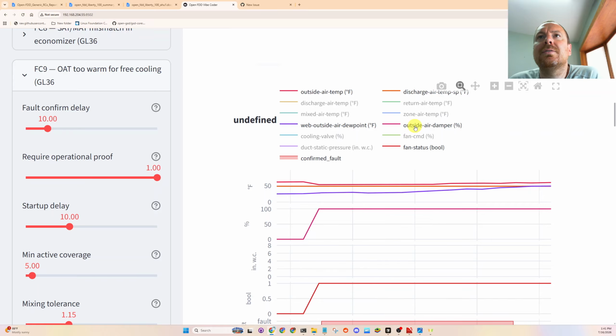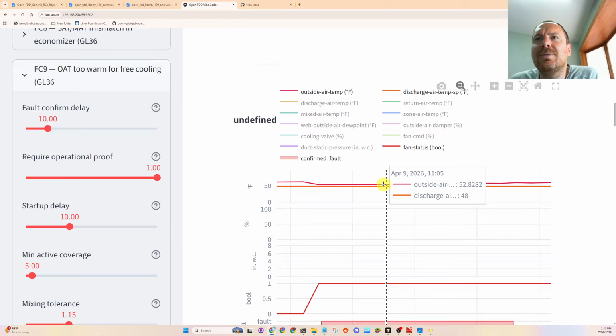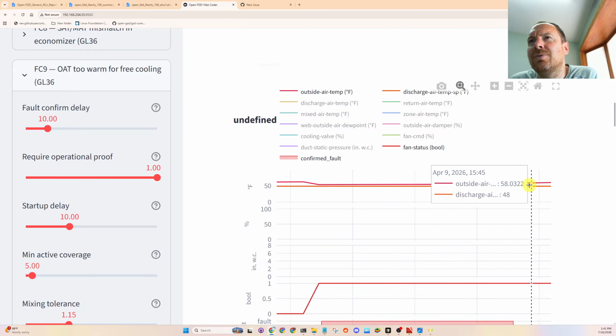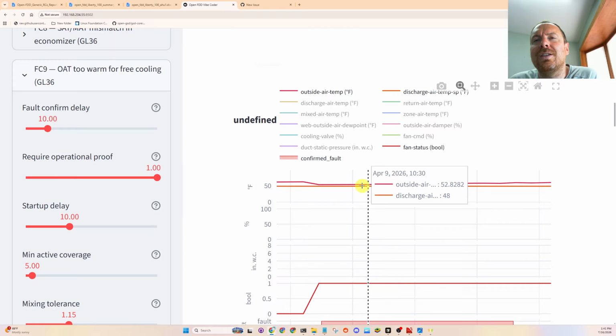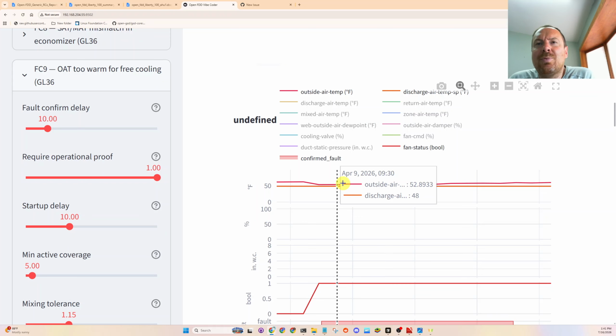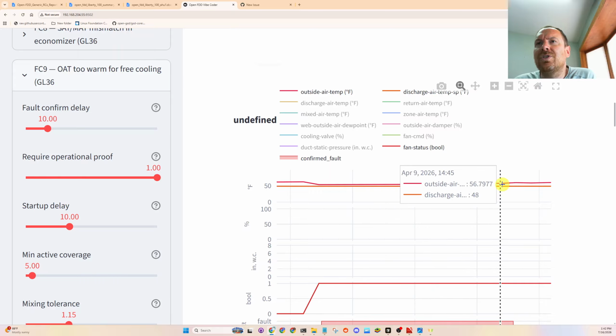Let's look at this. Get rid of that. Let's look at the dupe. Get rid of that too. Okay, so outside air temperature, discharge air temp set point is 48. So yeah, this is a really cold unit. Okay, so this is probably screwing up the equation. The discharge air set point is 48 degrees, which is something that we've flagged as being kind of odd already, having a really low discharge air temp set point. So it's causing this fault equation to get screwed up.